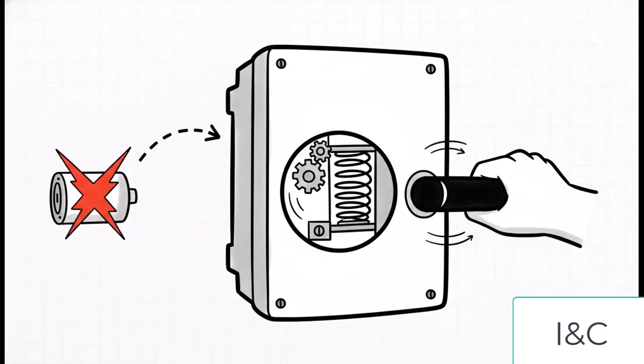And you can't miss this big black handle, right? That's the manual charging handle. See, these breakers use a crazy powerful internal spring to operate, and that spring needs to be charged up with potential energy. Usually a little electric motor does that automatically, but this handle is your crucial manual backup. If you lose control power, you can still walk up, crank this handle, and get the breaker working.